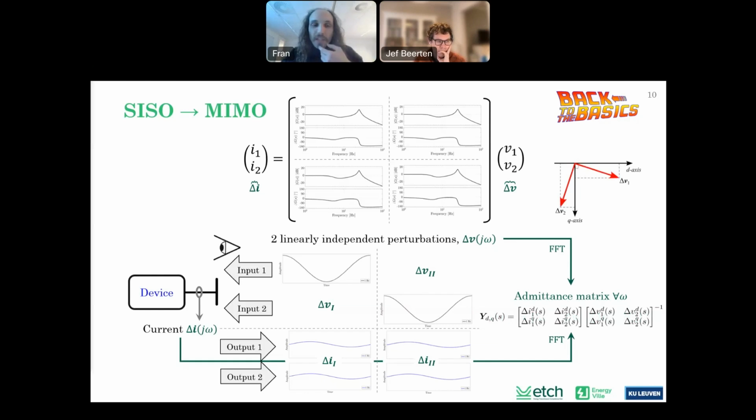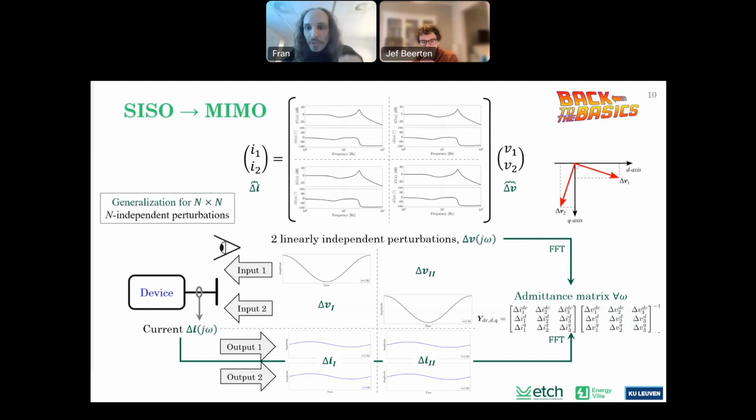And the same extends to other systems. So if we had, for instance, a power converter, which usually has an AC and a DC side, then we need two quantities for the AC side and one quantity for the DC side. That makes a 3x3 matrix. And this can be generalized to any kind of subsystem based on the description of the subsystem itself. So it can also be generalized to any multi-feed networks.